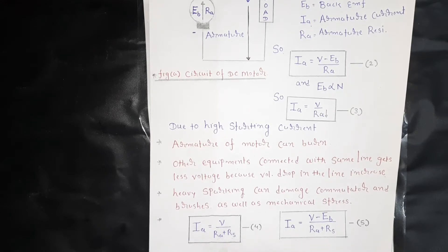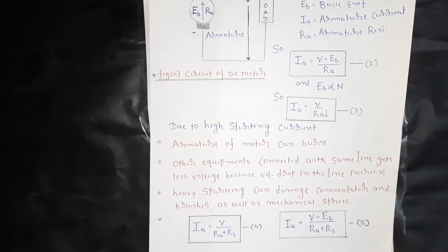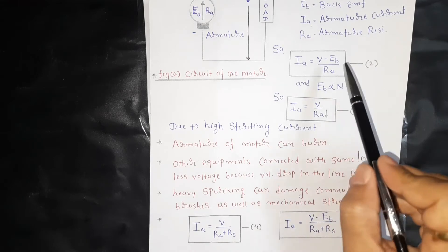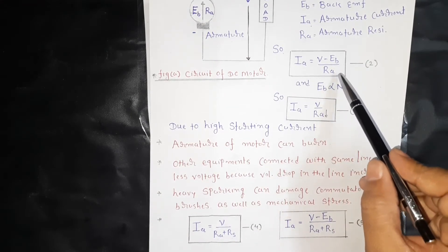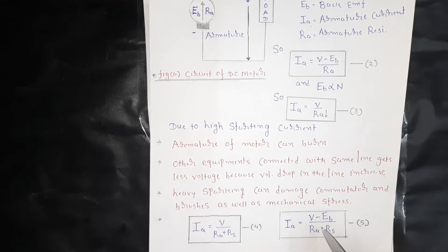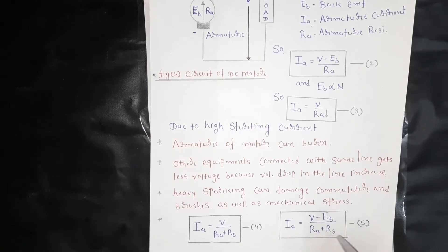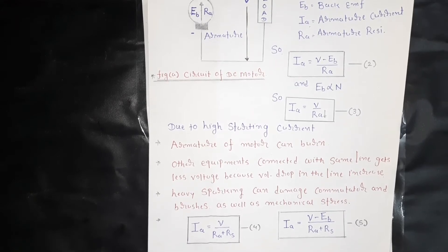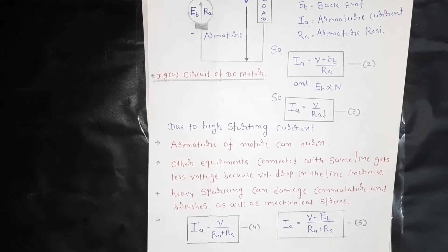This starting resistance does not need to be present throughout the full operation of the DC motor. Because as the speed of the DC motor increases, the back EMF also increases. This back EMF will counter the supply voltage, as shown in equation number 5: IA equals V minus EB divided by (RA plus RS). As the speed increases, back EMF increases, and when the back EMF reaches its maximum value, the starter decreases the starting resistance and ultimately cuts out all starting resistance to zero. The main purpose of the starter is to reduce the starting current to a very safe value so the DC motor cannot be damaged.